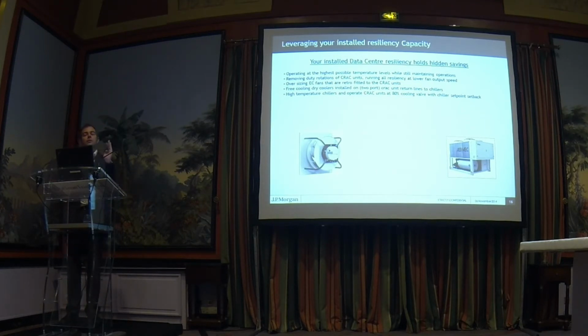So you run your CRAC units at 90% valve opening. You make a bit of logic that looks at all the CRAC units on average. If that average goes above 90, 95, you then automatically send a signal to the chiller to set a set point from, say, 18, 19 degrees, and put it down 1 degree at a time until the valves start to come back. When the load on the data center begins to back off, that valve opening will begin to close down on all the CRAC units, and then it goes, oh, okay, I'm 10% below, I'm now at 80% or 70% valve opening. That will trigger some logic in your BMS to put the set point back up.